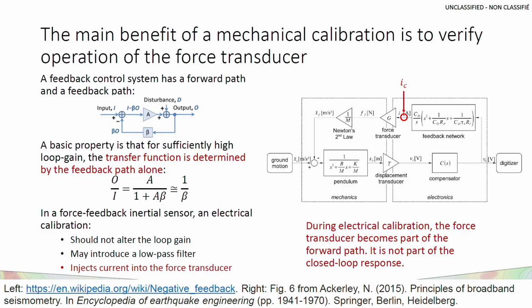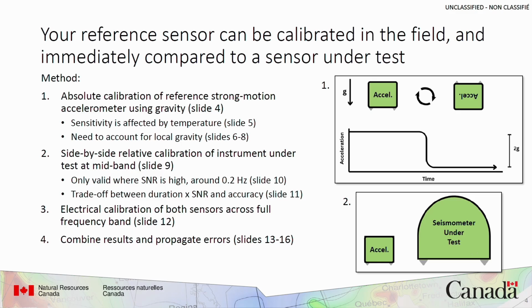The other thing I should note here is that those force feedback transducers are typically magnets with coils wound around them, and the magnet strength and the coil resistance can both be temperature dependent. So for me, knowing this, I'm proposing to only try to do absolute calibration at mid-band in the field. And really focus on this one otherwise unmeasurable by electrical calibration parameter, the force feedback transducer.